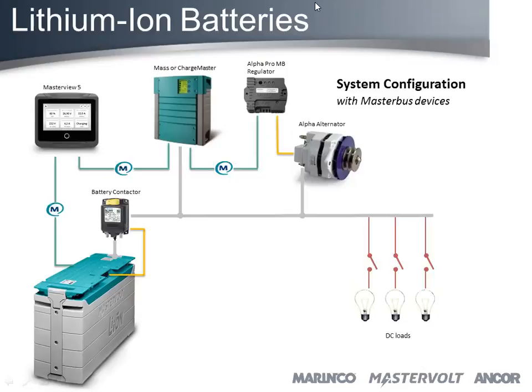If you have a single battery in a boat, that could be a problem because then you have a dead ship. But if you have multiple batteries, you put multiple latching relays in, one for each battery. If there's an issue with one of the batteries, it takes itself offline, so in theory we would never reach the scenario you were just describing.